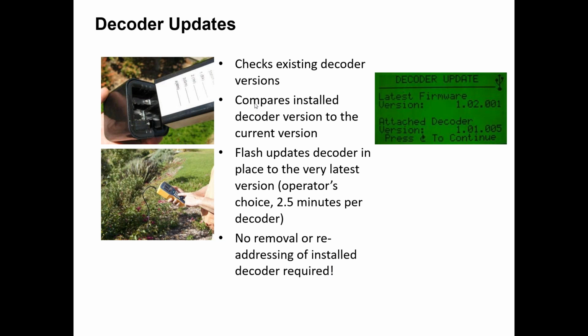It is a handy tool. You can also, as I said before, each one of these decoders has a firmware version on it, and they can be updated through the ICDHP. By putting it in there and going to the firmware screen, it'll look and see what version is on the decoder, and then it'll compare what is on the decoder to what you have on your ICDHP. And then from there, if it needs to be updated, you can update it. It takes about 2.5 minutes per decoder. So start it up and there'll be a progress bar. And then once you're done, you don't have to remove it. You're good to go.